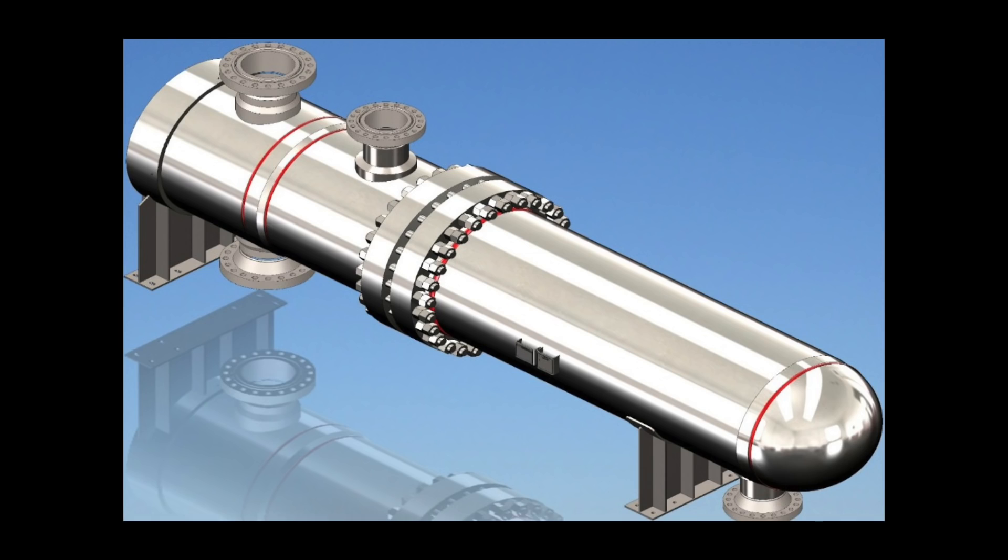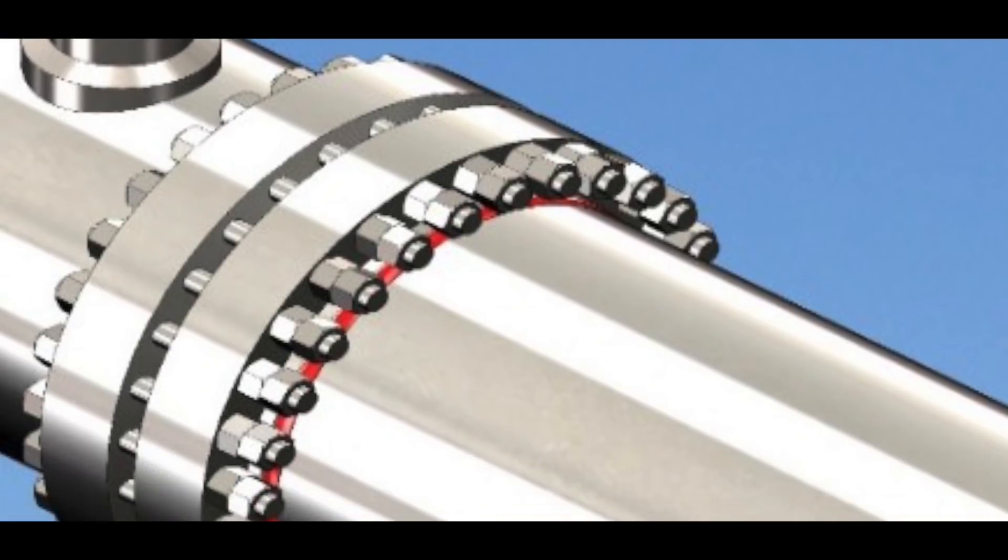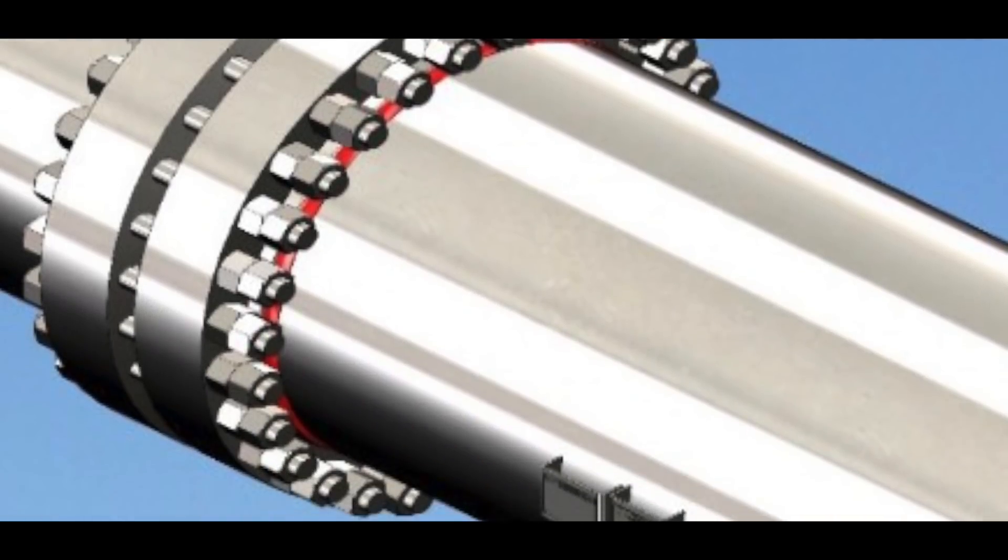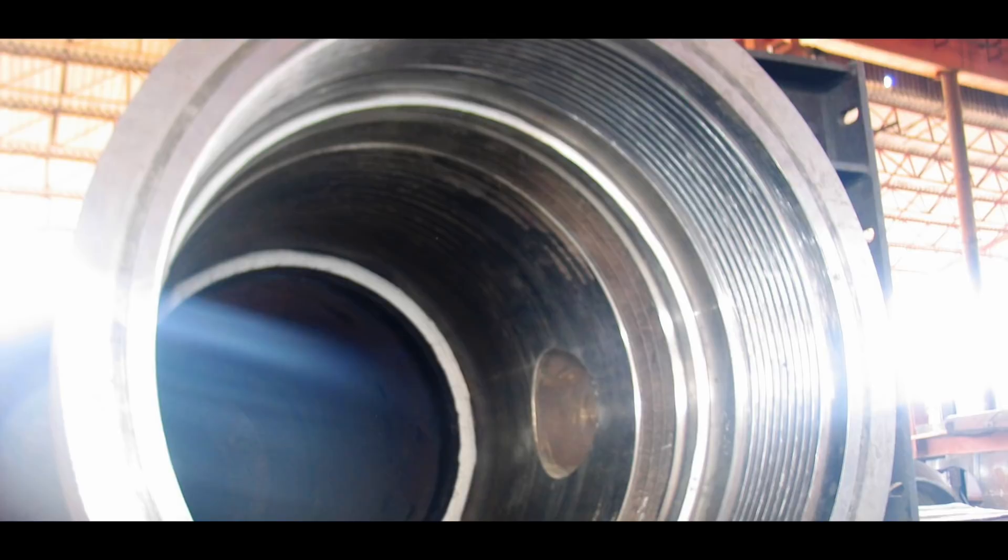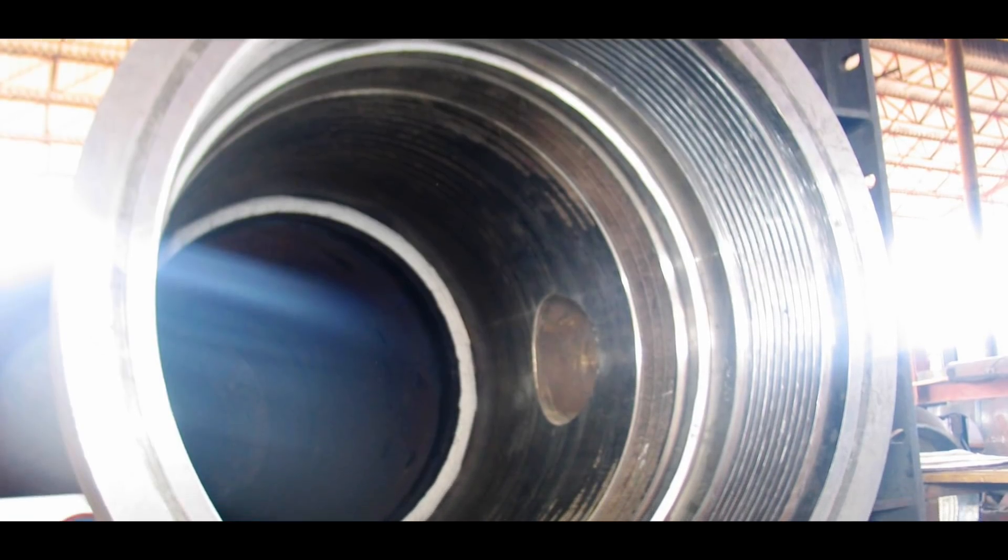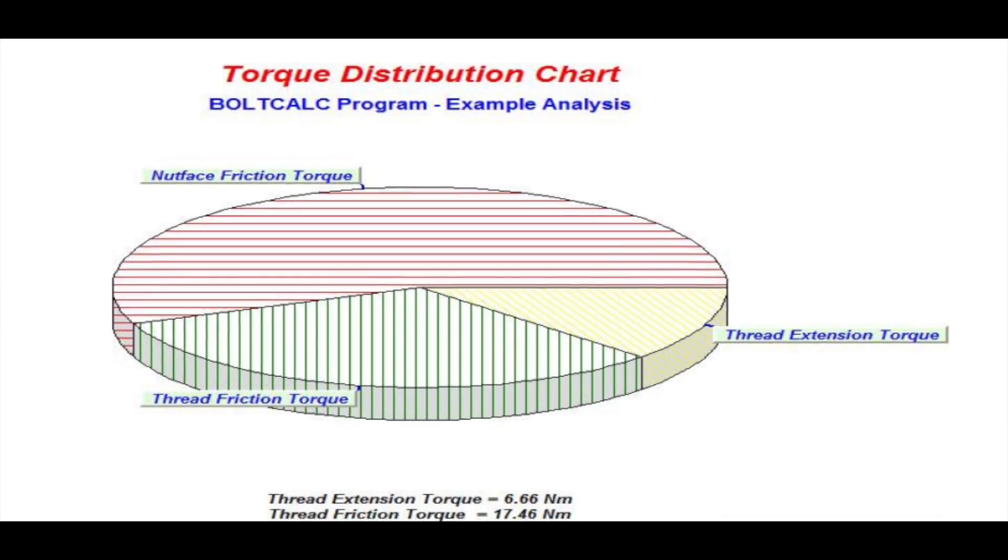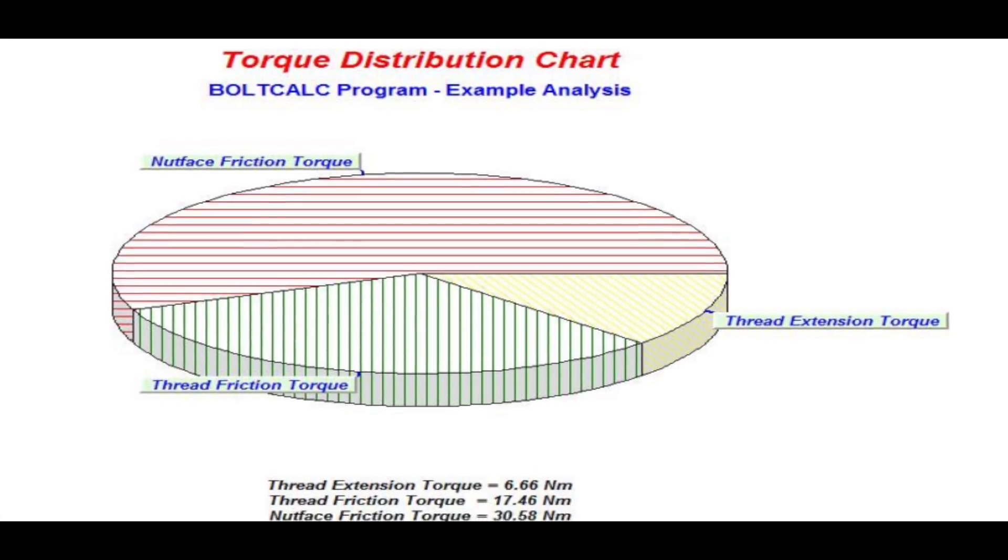Point 5: Tightening procedures should be such that the minimum load applied is uniformly distributed throughout the gasket. This is because the key element is the axial load on the gasket at each bolt location and not the torque applied.